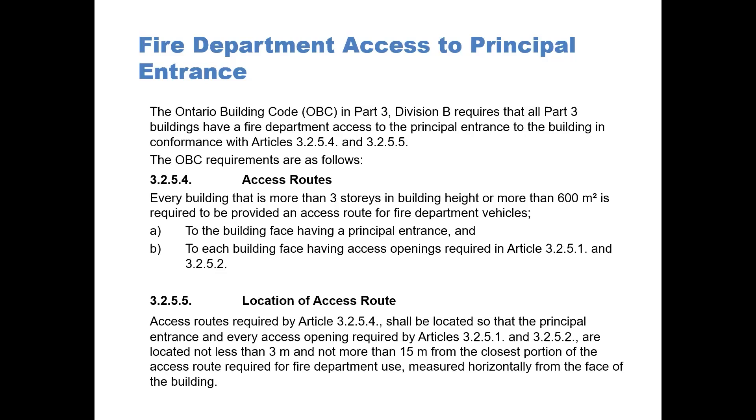The OBC requirements are as follows. Article 3.2.5.4 — access routes: every building that is more than three stories in building height, or more than 600 square meters, is required to be provided with an access route for fire department vehicles to the building face having a principal entrance, and to each building face having access openings required by Articles 3251 and 3252.